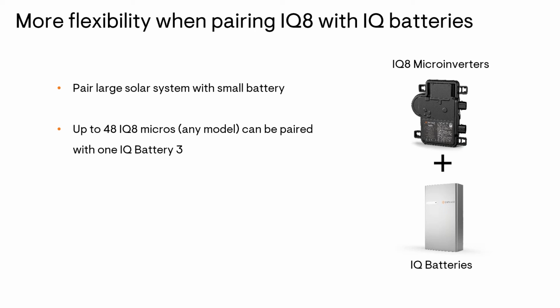So a little bit more about the flexibility that designers have now with the IQ8s. And this is related to that 1.5 to 1 ratio that I mentioned earlier. So with the IQ8s, you can pair a relatively large solar system even with just a small IQ battery 3. So the limit is actually the same for all different models. Now up to 48 IQ8 micros can be installed, and that's any of the models that we have, if a single IQ battery 3 kilowatt hours is being installed. That's a much, much greater flexibility compared to that 1.5 to 1 ratio.